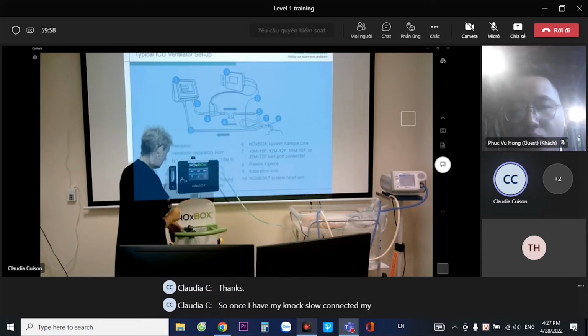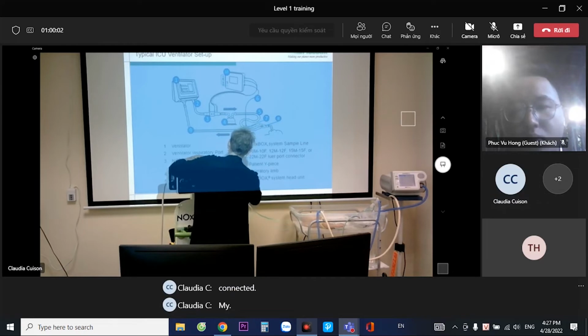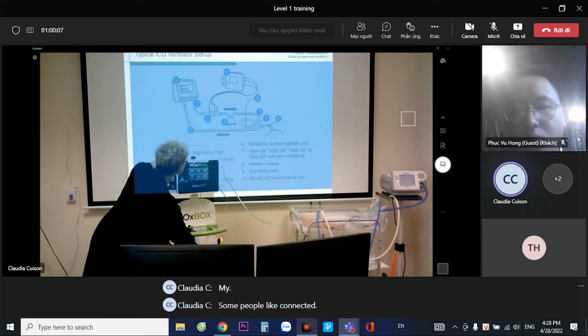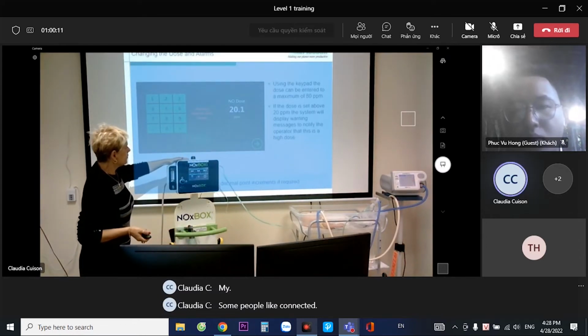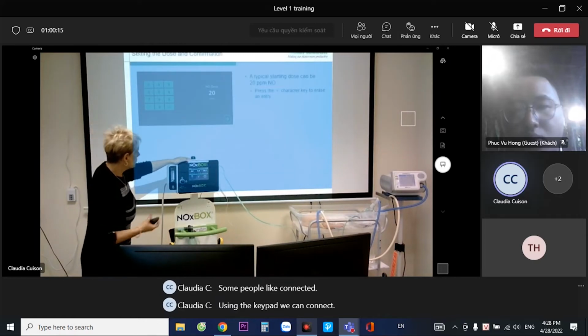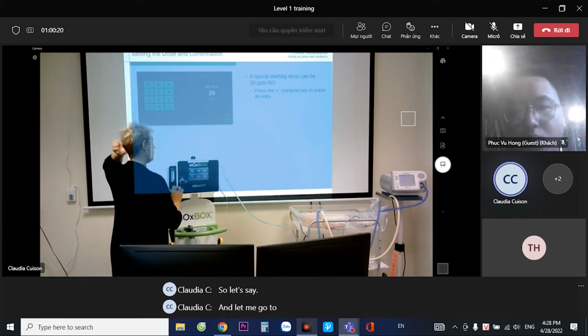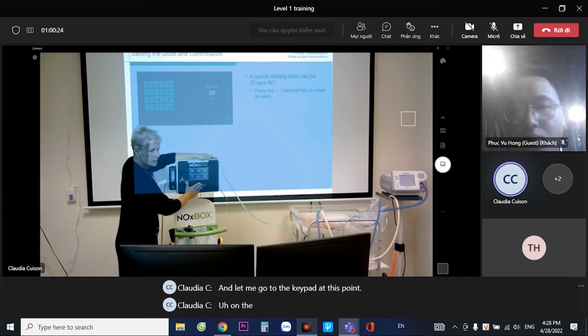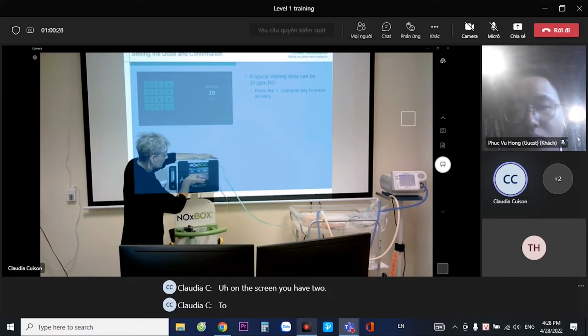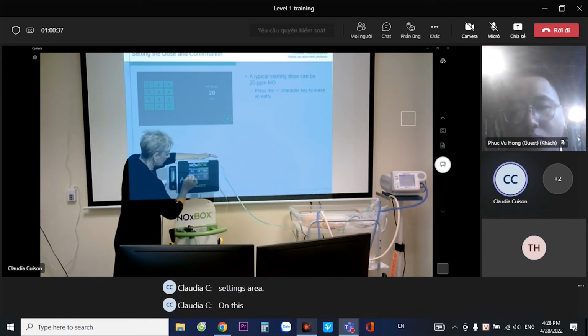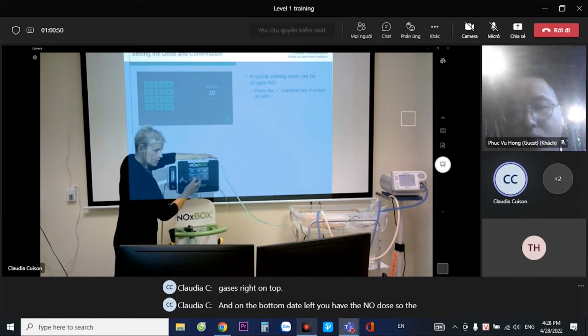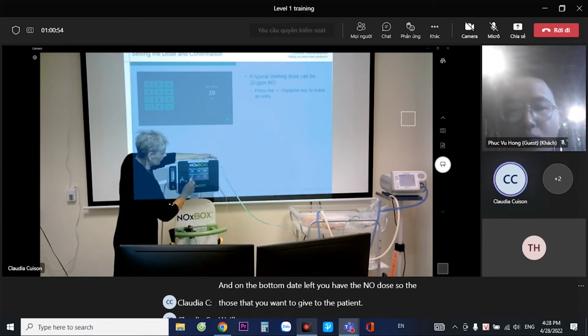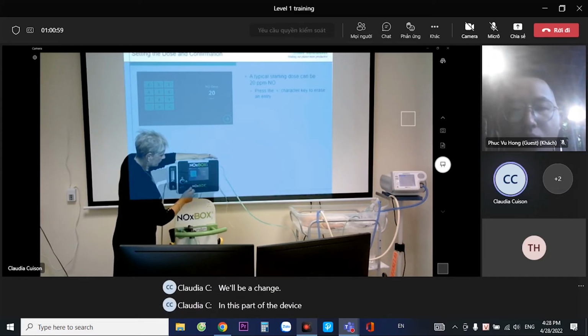So once I have my NOxBOX connected, my ventilator connected, my sample line connected, using the keypad, let me go to the keypad at this point. On the screen, you have two sides or areas. This is the monitoring area, and this is the settings area. On this side, we are going to see the monitoring of the three gases, right, on top. And on the bottom left, you have the NO dose. So the dose that you want to give to the patient will be changed in this part of the device.